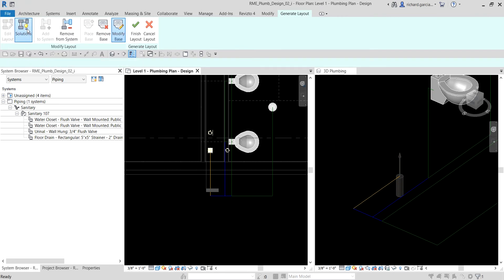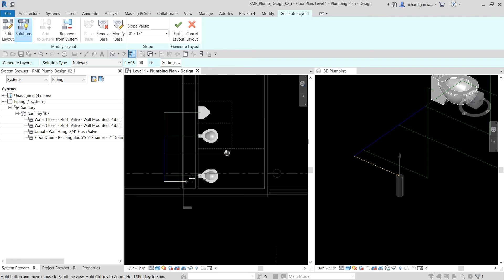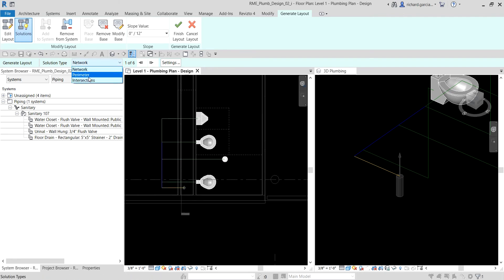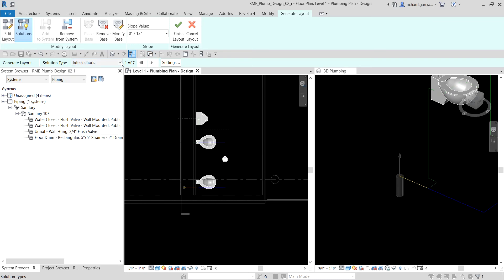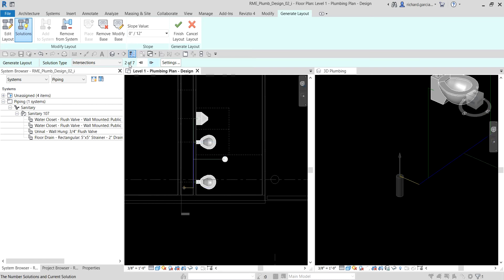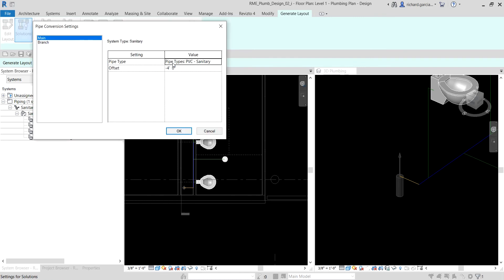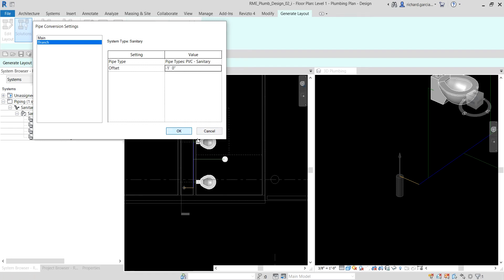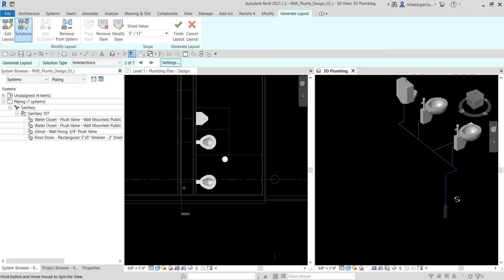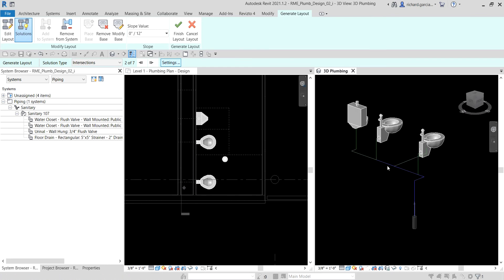Let's modify the base. I'll go to Solution and change the solution type from Network to Intersections. We have seven solutions — I want solution two of seven. I'll select Settings and change the main pipe (the blue pipe) from minus four feet to minus one foot, and the branch the same — minus one foot. I select OK, and there's no more problematic pipe — just blue for the main pipe and green for the branch.